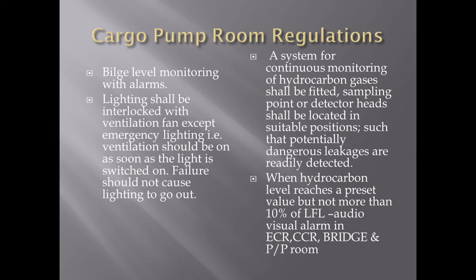The second regulation is very important and technical: lighting shall be interlocked with the ventilation fan, except emergency lighting. This means ventilation should be on as soon as the light is switched on. However, if the ventilation goes out, that does not mean the lighting should also go out. So there is an interlock provided between them.